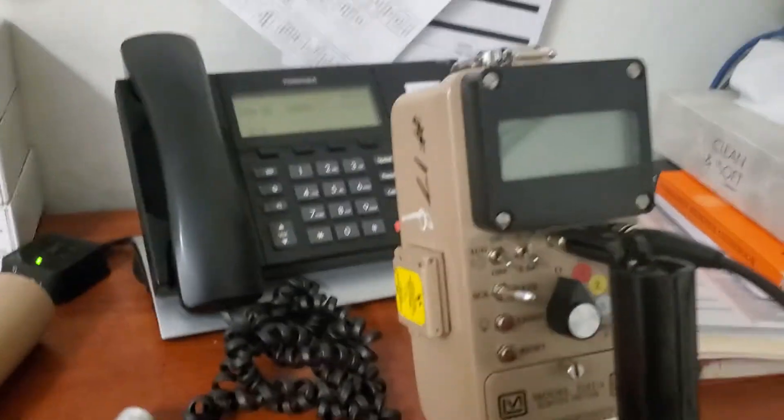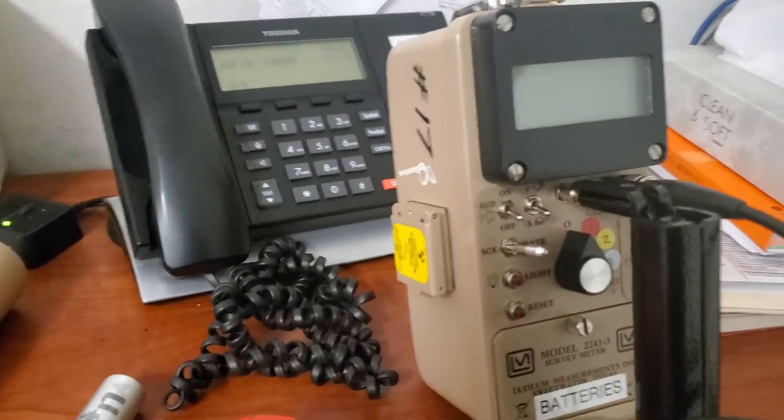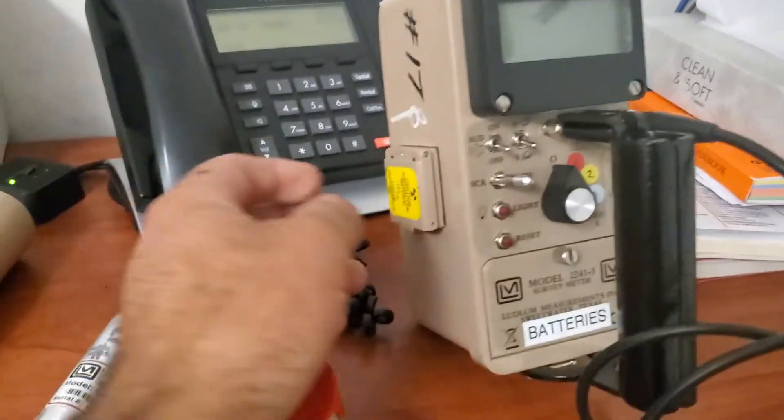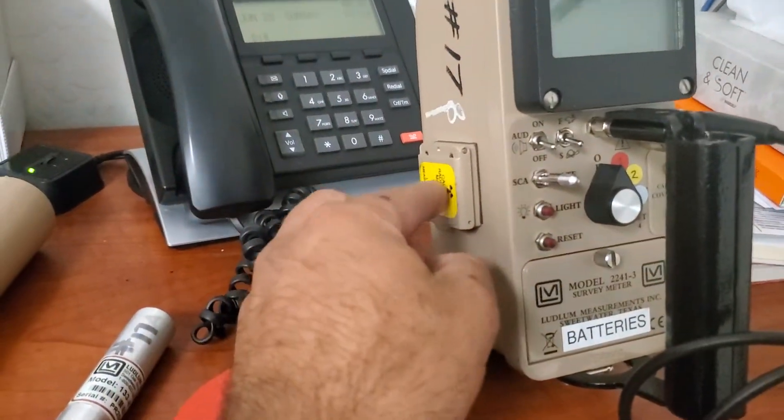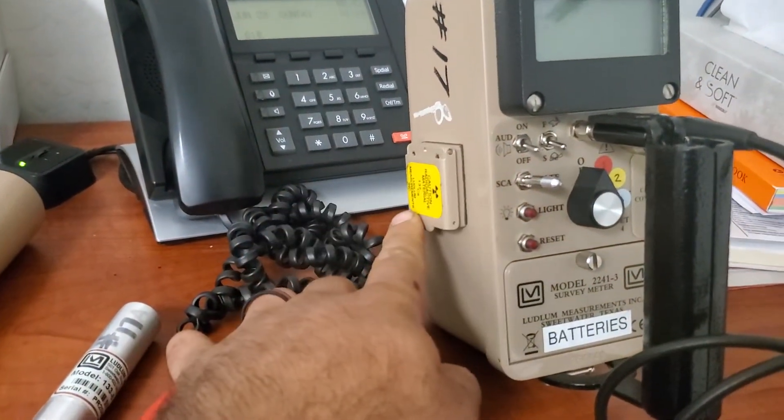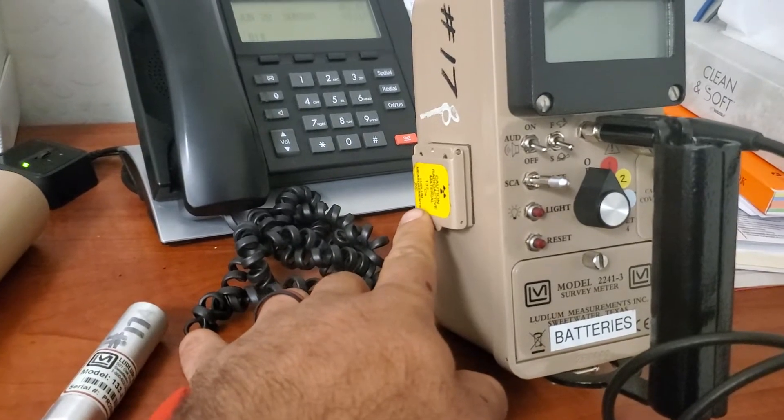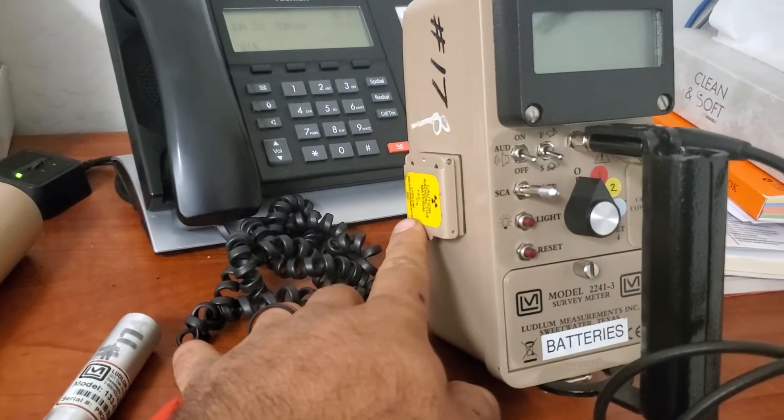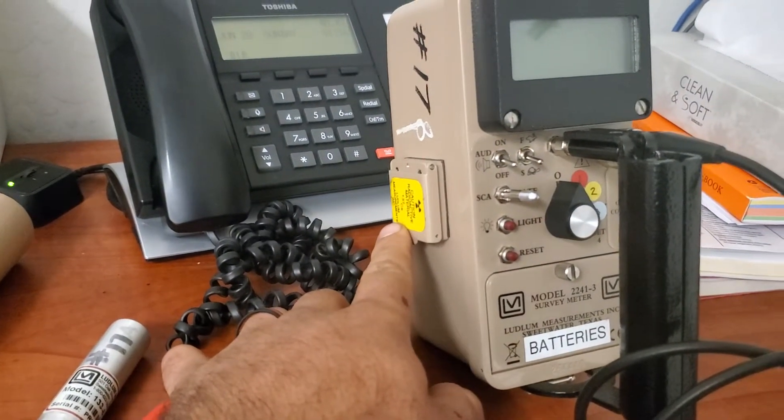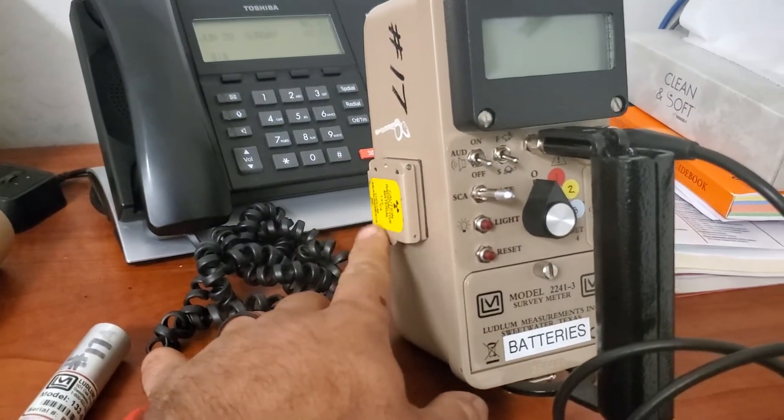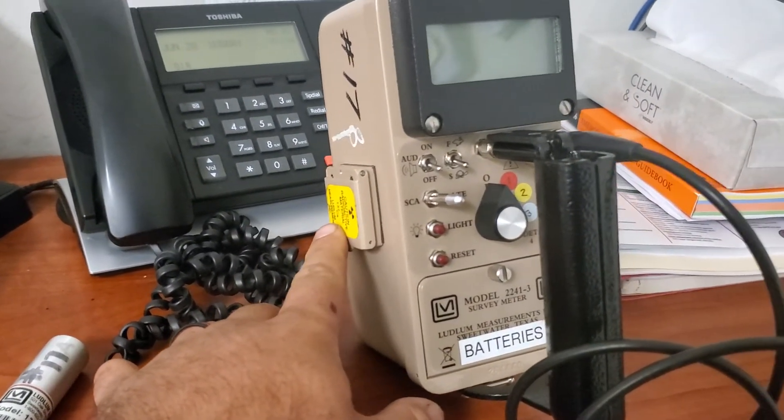A brief overview of the meter. Right here on the side we have a check source. This is Cesium-137. It's a beta and low-level gamma emitter, but primarily beta.